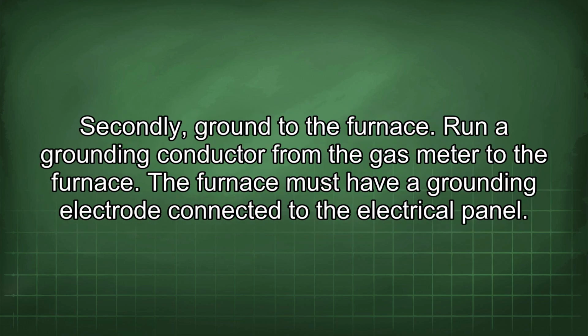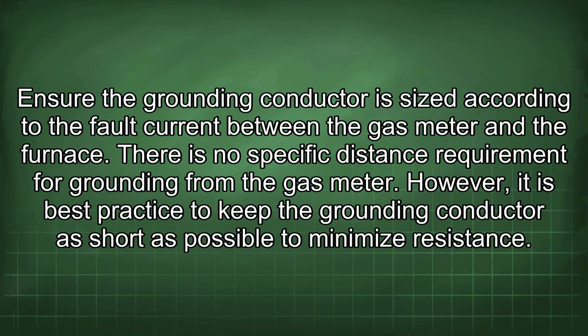Secondly, ground to the furnace. Run a grounding conductor from the gas meter to the furnace. The furnace must have a grounding electrode connected to the electrical panel. Ensure the grounding conductor is sized according to the fault current between the gas meter and the furnace. There is no specific distance requirement for grounding from the gas meter. However, it is best practice to keep the grounding conductor as short as possible to minimize resistance.